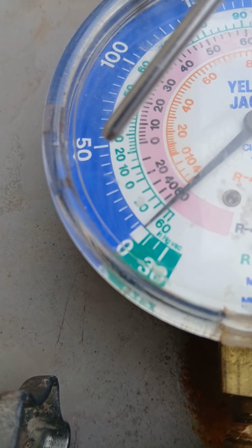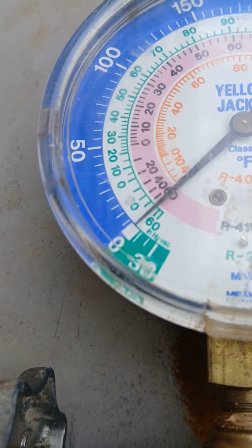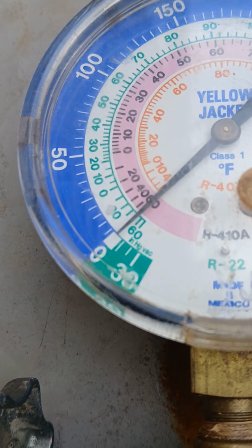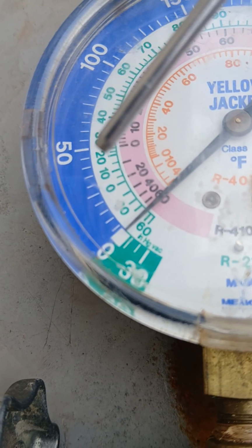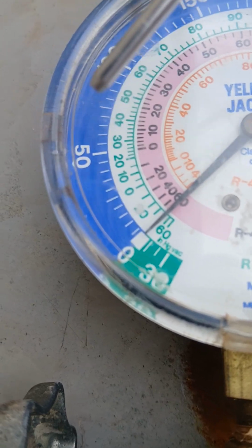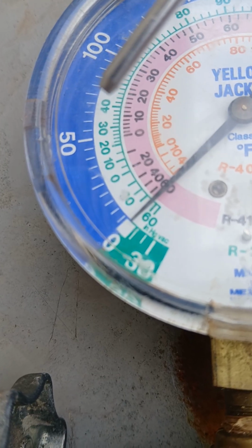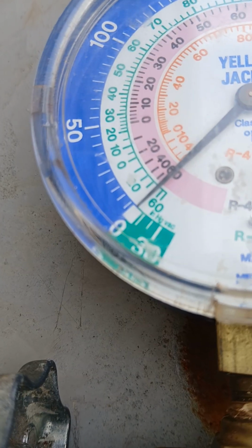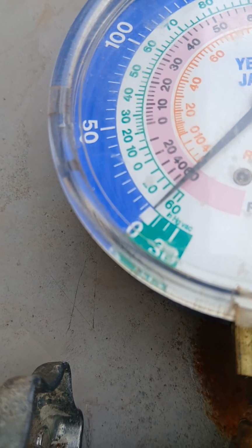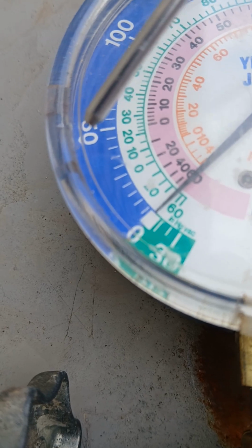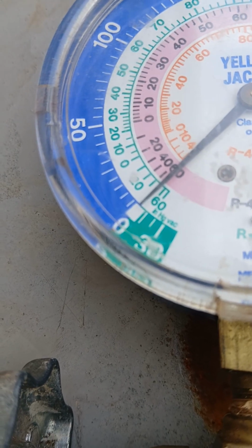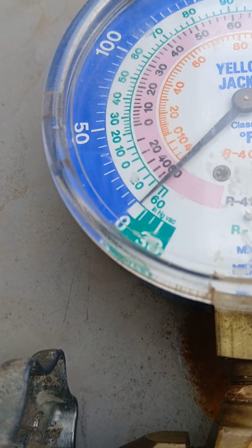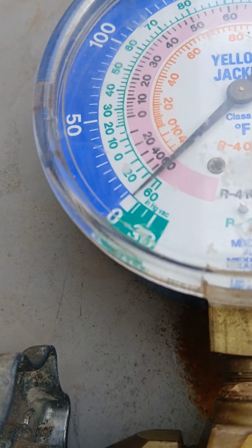So here's your answer. The gauges can tell you a lot about what's going on with the HVAC system. If the Psig is low, the temperature may be low. If the Psig is high, the temperature may be high. Somewhere in this range here may be good. We just do not want to get below 32 degrees. If you get below 32 degrees and you're reading a low pressure on your gauges when you hook them up, this could indicate why there may be ice on the suction line or the low pressure line.